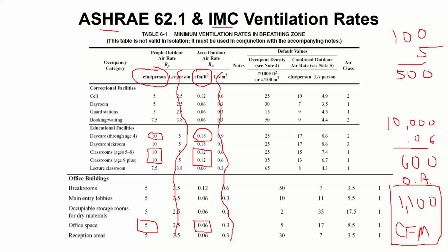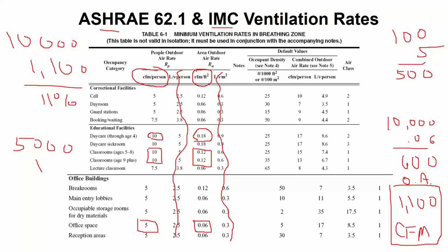Then unrelated to that, we'd figure out how much outside air we need, which is this table here. Right? So I might have, like I said, an example where I need 10,000 CFM of total air, but now I have to get 1,100 from the outdoors, right? So that's 11%. If you guys can follow my chicken scratch with the mouse, you're saints. But then I may also have a different space that is only 5,000 CFM of cooling needed, but I still needed the 1,100 CFM of outside air, right? So that one's 22% outside air.